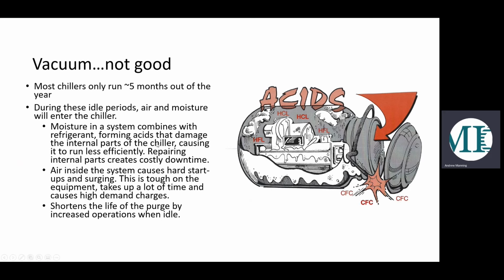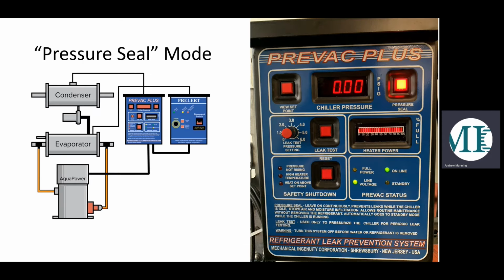This is addressed by the purge unit, but we see that as more of a reactive measure, and PREVAC is more of a preventative maintenance measure. So we address that with our pressure seal mode, and the name hence, prevention of vacuum. So when the chiller shuts down, the system goes into a vacuum and the pressure drops below our set point of 0 pounds, which we read with the transducer that's on the condenser here, and it feeds into the PREVAC controller. That's going to activate the pump. That's going to pump hot water through the evaporator, and that's going to warm up the refrigerant and bring the system back to pressure equilibrium.